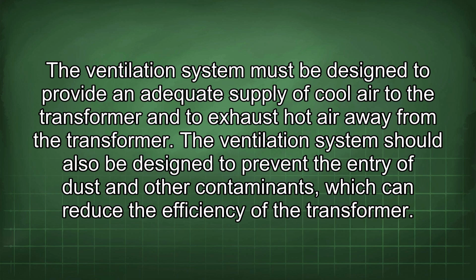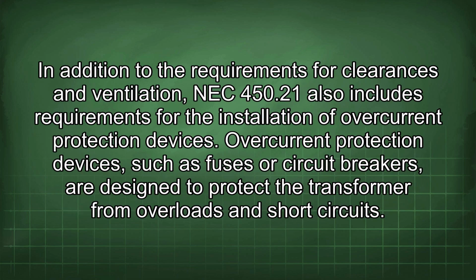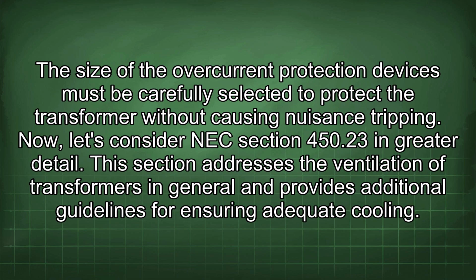efficiency of the transformer. In addition to the requirements for clearances and ventilation, NEC 450.21 also includes requirements for the installation of overcurrent protection devices. Overcurrent protection devices, such as fuses or circuit breakers, are designed to protect the transformer from overloads and short circuits. The size of the overcurrent protection devices must be carefully selected to protect the transformer without causing nuisance tripping.